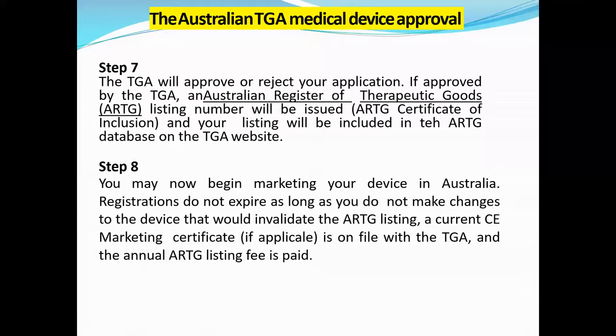What does it mean? The TGA will approve or reject your application, right? If approved, we get the ARTG number. If it is not approved, then it will not be listed. Once you get the ARTG number, your product will be listed on their website, so you may now begin marketing your device in Australia. Registration does not expire as long as you do not make changes to the device that would invalidate the ARTG listing, the current CE marking certificate, if applicable, is on file with the TGA, and the annual ARTG listing fee is paid.